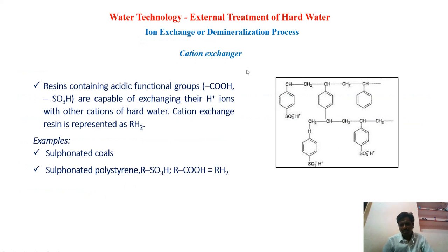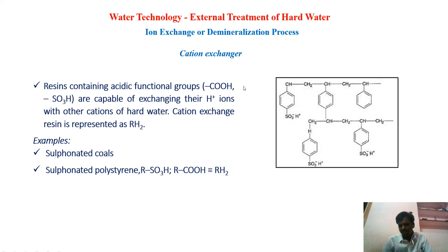The first type is the cation exchanger. These are linear polymers, possibly styrene molecules, with cross links. These molecules have a sulfonic acid group — SO3⁻ H⁺. These functional groups carry positive H⁺ ions, which can be replaced with calcium and magnesium ions present in the water. When you pour that water, calcium and magnesium ions replace the H⁺ ions, forming SO3⁻ Ca²⁺ or SO3⁻ Mg²⁺ on the resin. Sometimes the functional group may be a carboxylic acid group — COO⁻ H⁺ — where H⁺ is also replaced by Ca²⁺ from the water.